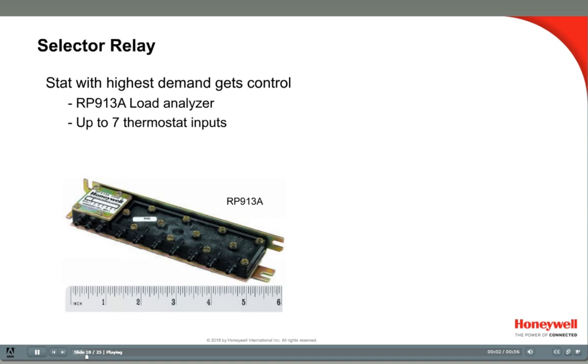Another selector relay is the RP-913A load analyzer. It selects the highest or lowest branch pressure input from zone thermostats. It will select the highest pressure demand in cooling applications or the lowest pressure demand in heating from up to seven thermostats, and pass this signal on to the heating or cooling device. Two load analyzers can be connected together to get 12 inputs. There is no calibration needed on the RP-913. The only service necessary is an air filter. If the output pressure is more than 1 psi below the input, the filter should be replaced. It uses the same filter as used on the thermostats, like the TP-970.